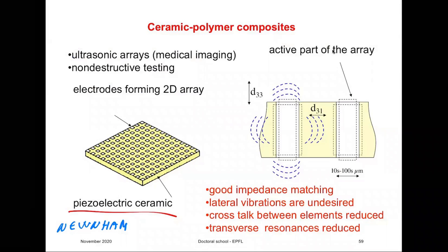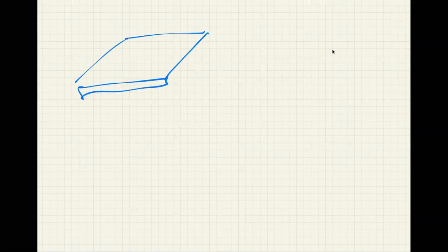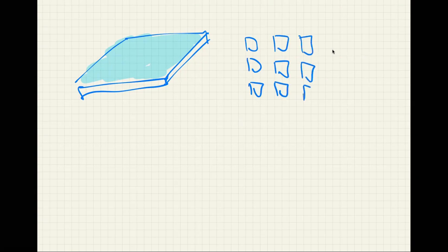So what can you do? Well, one of the things that you can do with these elements is to make arrays. So you can have a single element transducer in which you have a monolith sample electroded on the top, and the whole sample oscillates. But sometimes what you would like to have is an array of transducers, and I am now drawing this from the top. An array of transducers where you can scan.